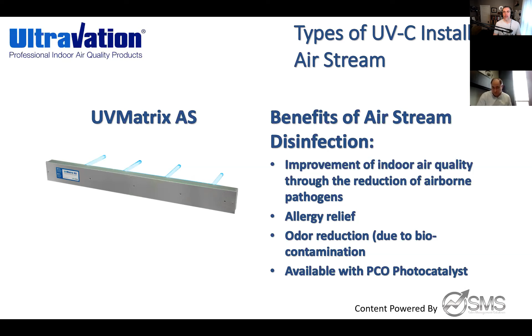This is why we have to really talk design. That design, when they need to go one on each side of that main duct, so the bulbs meet in the middle to ensure at least, I think the standard is 80% coverage in an airstream ductwork. It depends on the ductwork and the design. If you're dealing with a small supply duct, you might be able to have just one of these installed.